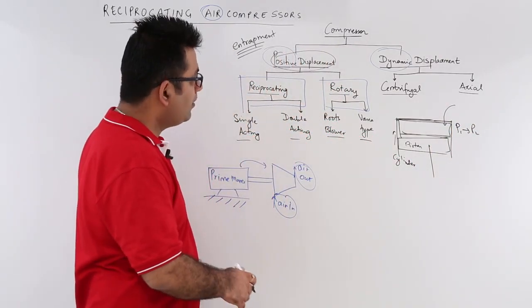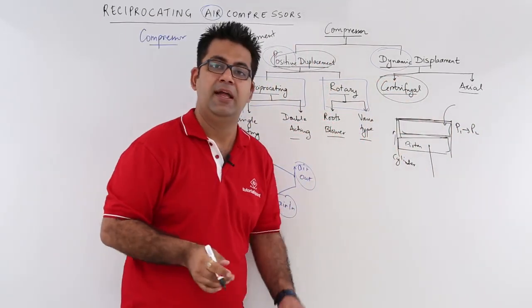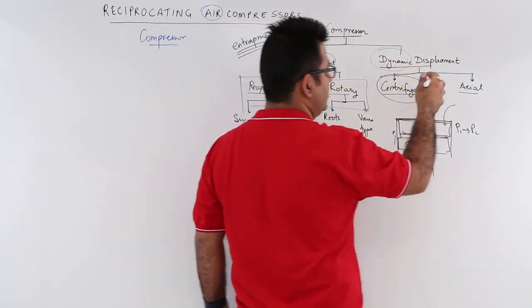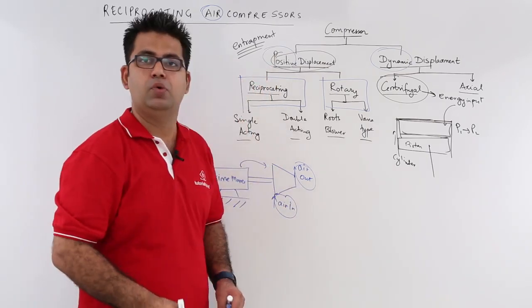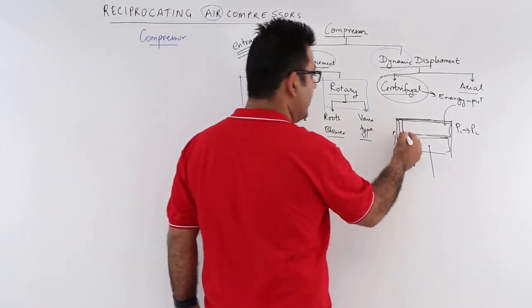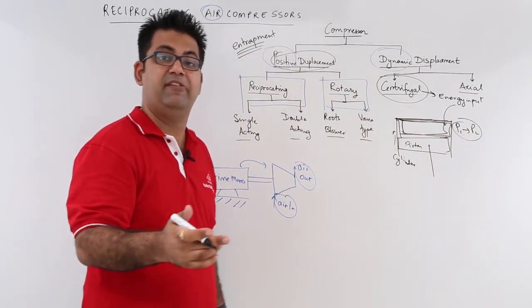But if you talk about dynamic displacement — for example, centrifugal — the entrapment of the fluid is not there. The pressure increase is majorly due to energy input. You provide energy to the moving air and it goes out at a higher pressure. Because in positive displacement you are entrapping the fluid inside a volume and pushing it against a fixed surface — the cylinder head — the pressure increase from P1 to P2 is very, very high.